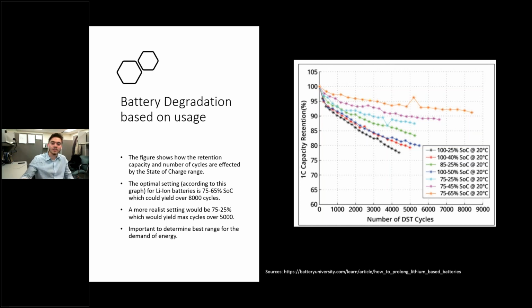For industry purposes, the best thing to do is determine how much energy demand you'll need. If you can have a shorter discharge and charge range, like 75 to 65%, use that and your battery will last much longer. However, in more cases we see today in the United States, industries are using 75 to 25% and achieving that 15-year mark. The next slide will show an example of that.